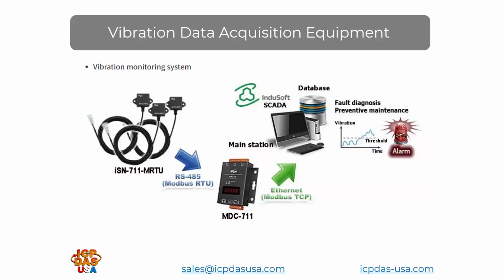Vibration data acquisition equipment. In this system, we have the ICP DAS ISN 711 MRTU vibration sensors, which communicate via Modbus RTU to our MDC 711, which is a data concentrator that logs vibration data. The MDC 711 allows up to 8 Modbus TCP masters to pull data, and it can pull data from multiple Modbus RTU slaves in addition to the vibration sensors. The computer running the Indusoft SCADA system with an HMI control panel communicates via Modbus TCP to the data concentrator. Through the Indusoft project, we analyze and log data to a database. When the vibration exceeds the threshold that indicates the beginning of a problem, emails are sent and maintenance is scheduled.